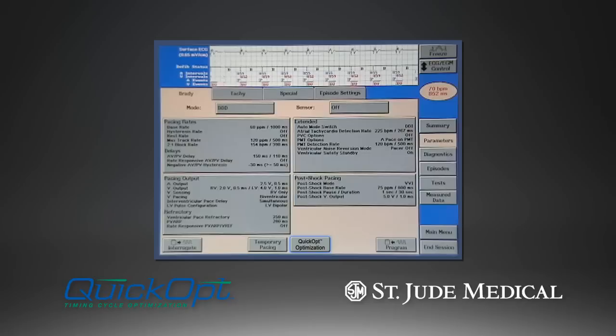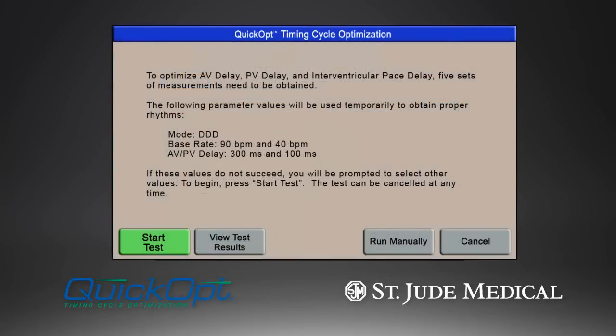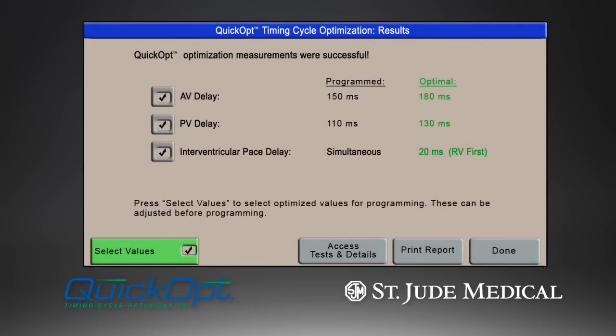The QuickOpt feature can be found on the Brady Parameter screen. Pressing the QuickOpt optimization button opens the Start Test screen, where the programmer lists temporary settings that will be used for the series of five tests. The Start Test button initiates the testing sequence, and about a minute later, the results screen appears with the calculated optimal delays. Each calculated delay may be accepted or rejected simply by pressing the individual check marks, then pressing the Select Values button in the lower left-hand corner. Pressing the Done button returns the user to the Brady Parameter screen where any values selected will be batch stored. Pressing the blue Program button permanently programs those selected values into the device.